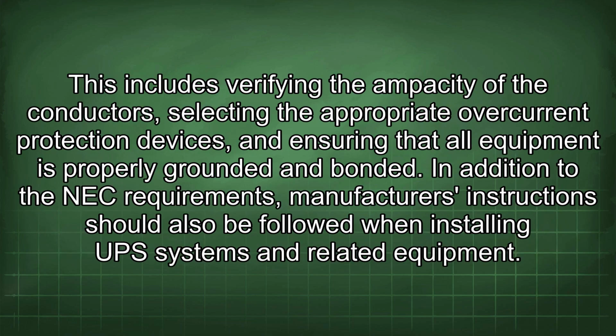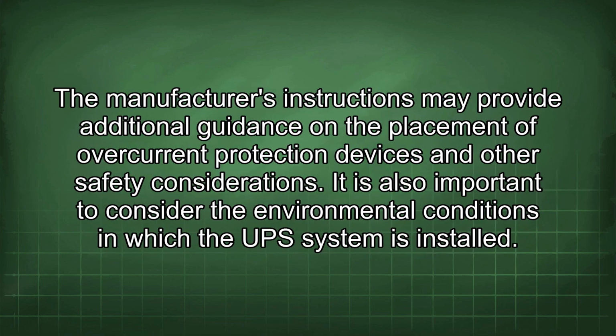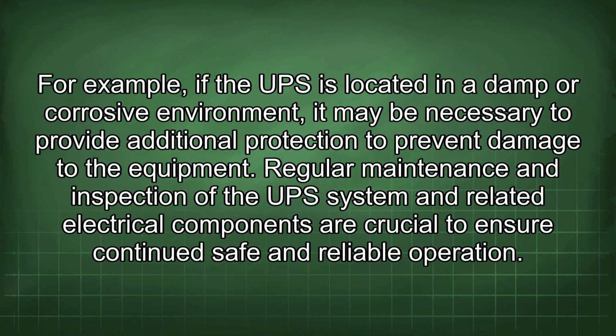This includes verifying the ampacity of the conductors, selecting the appropriate overcurrent protection devices, and ensuring that all equipment is properly grounded and bonded. In addition to the NEC requirements, manufacturers' instructions should also be followed when installing UPS systems and related equipment. The manufacturer's instructions may provide additional guidance on the placement of overcurrent protection devices and other safety considerations. It is also important to consider the environmental conditions in which the UPS system is installed. For example, if the UPS is located in a damp or corrosive environment, it may be necessary to provide additional protection to prevent damage to the equipment.